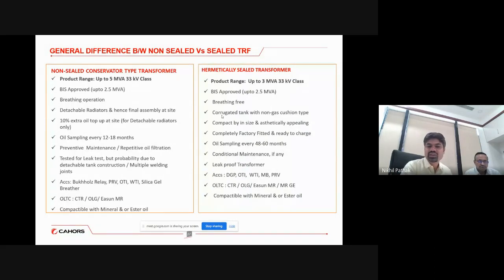So in case of the sealed transformer, we can tell you practically, it is not only that the transformer is charged in 1 month or 3 months or 6 months of the supply, but we have seen transformers actually charged more than 2 years and 3 years after delivery at site, and still the transformer has been charged without any troubleshooting, without any oil filtration at site, and it has really delivered the features and the concept which has been transferred by our French company in India. So this is the technological ground-level approach that we have already delivered.